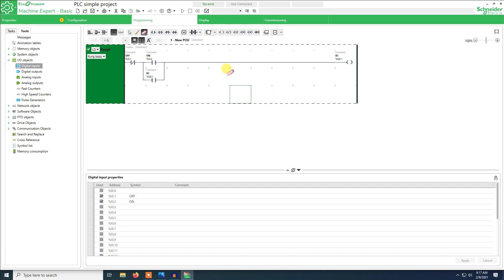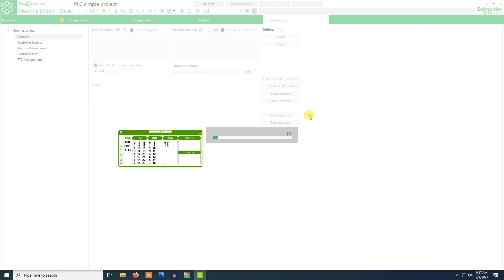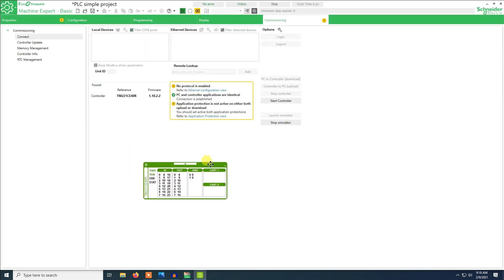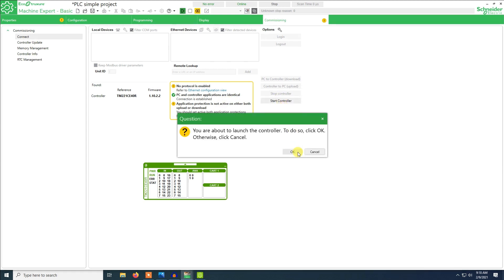Now it's okay. For testing of the PLC, we can run it in simulation mode. We go to commissioning and launch the simulator. Now we have to start the controller. Next we go to the programming tab — as you can see, the normally closed contact is active, it's green. Now I'm going to give it a command, and as you can see the output is active even though the input button here is off — there is no green color.